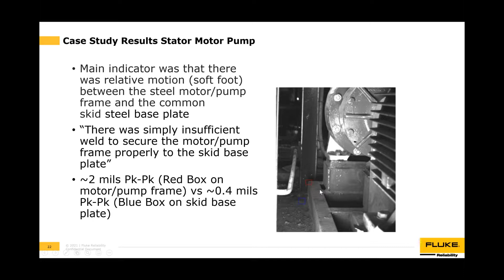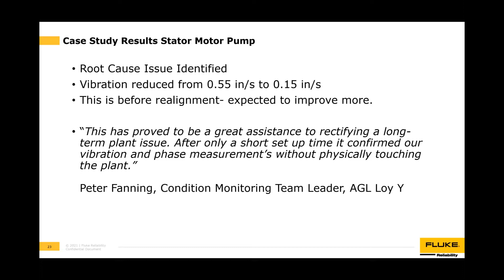Here again, we're hitting the root cause to identify it. It was just overlooked, and they didn't think to look at that. But with the camera, it could clearly see it. And it turns out now that is the duty pump. The pump that was the bad actor is now the duty pump, because it behaves better than what was the duty pump. So they've reversed roles, because they were able to get this in line so much. So again, that simple fix, but it's really identifying the location. Hindsight's 2020 once you see it, but being able to know to go there is really the battle.